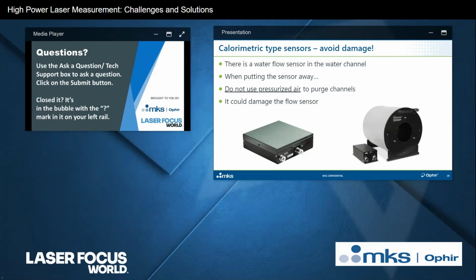There's a water flow sensor in the water channel that measures the flow rate of the water. And obviously there's a temperature sensor. Well, there's actually two temperature sensors, one that measures the temperature of the cooling water coming in, and the other one that measures the temperature of the cooling water going back out. So we know the temperature difference between those two. So we know the temperature increase and we know the flow rate. Very, very important tip.